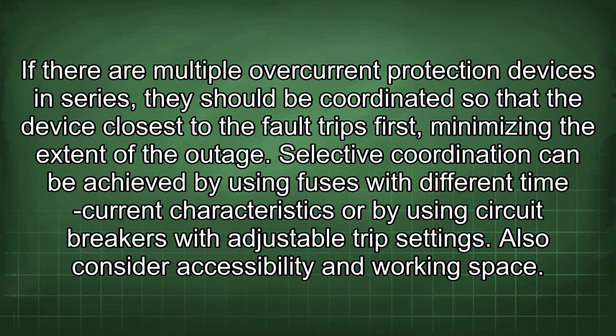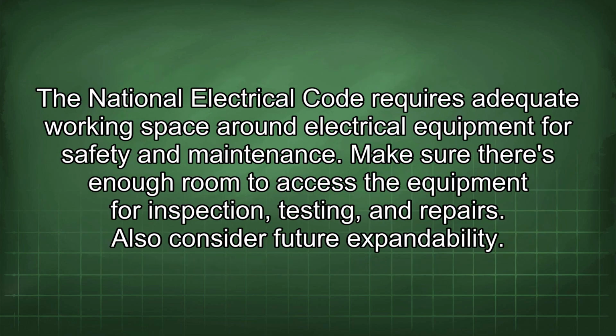Selective coordination can be achieved by using fuses with different time current characteristics or by using circuit breakers with adjustable trip settings. Also consider accessibility and working space. The National Electrical Code requires adequate working space around electrical equipment for safety and maintenance. Make sure there's enough room to access the equipment for inspection, testing, and repairs.